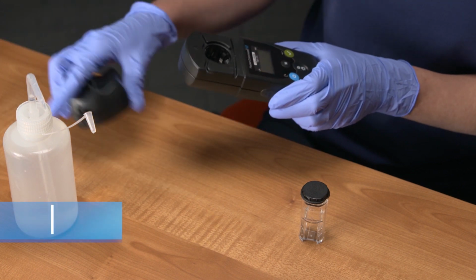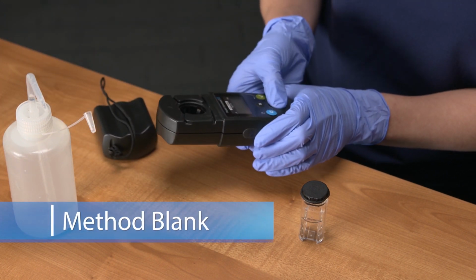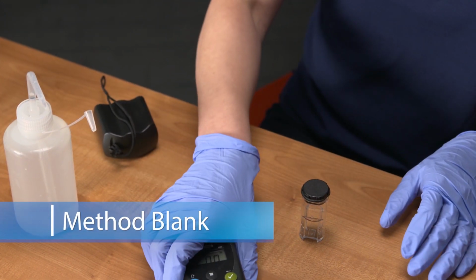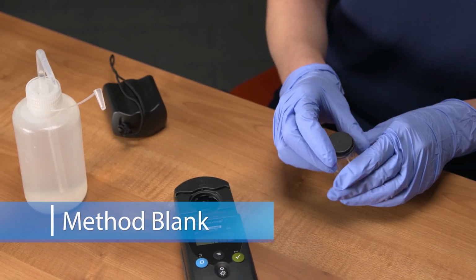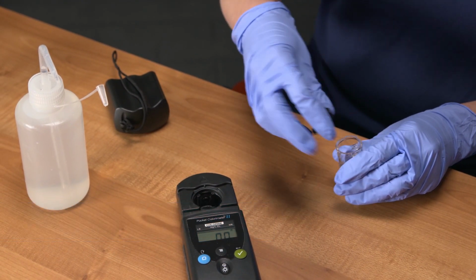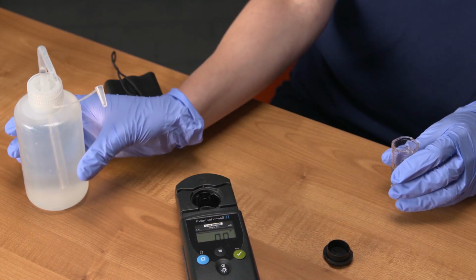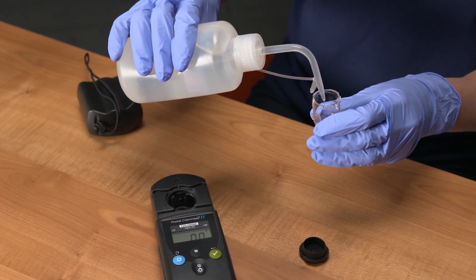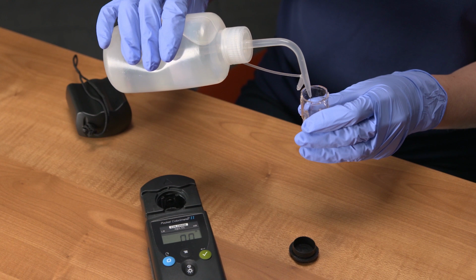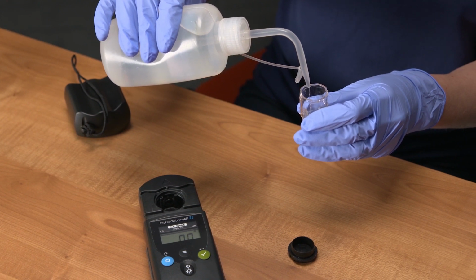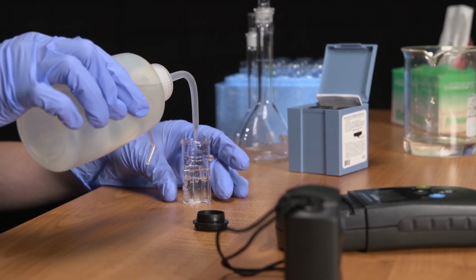Before performing any measurements, we will perform a method blank. A method blank is a measurement using reagent-grade water, where you follow the same analytical steps as you would for the standard measurements. The purpose is to determine whether there is any interference from our sample vial or reagents, so that we can account for that interference when measuring our standard concentrations.